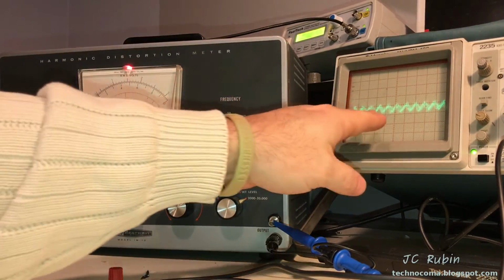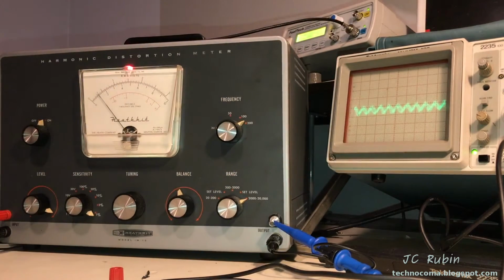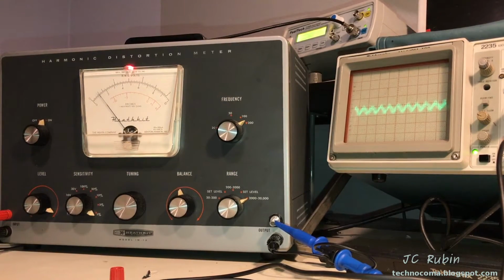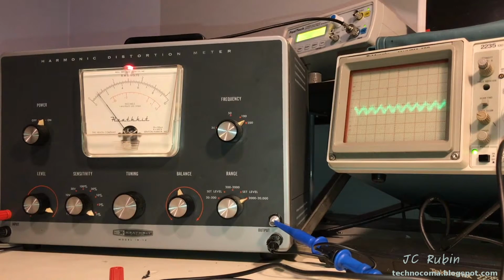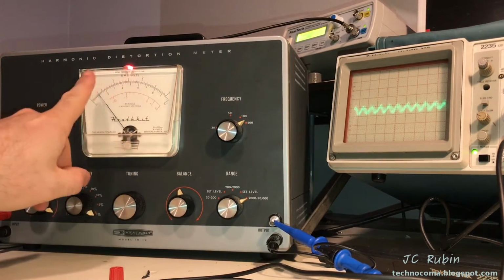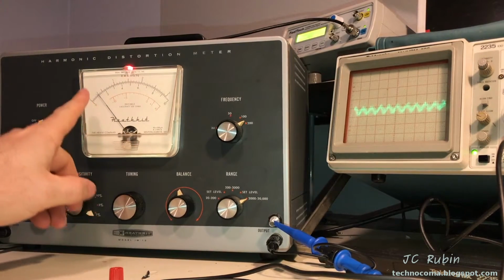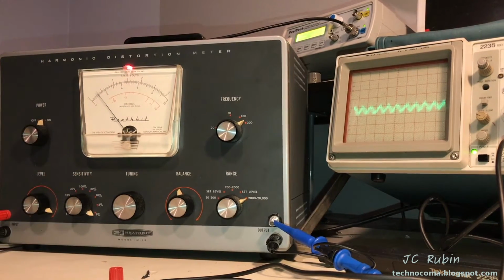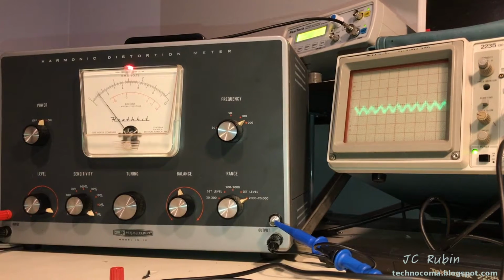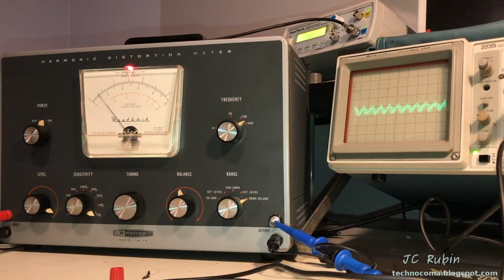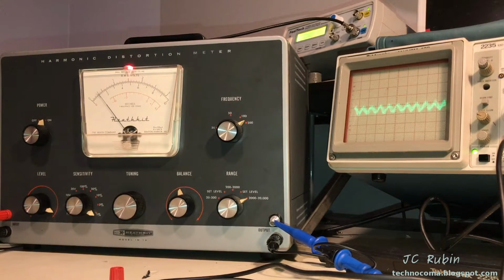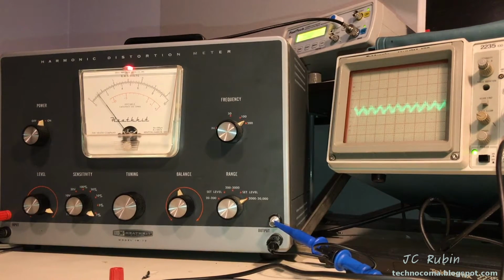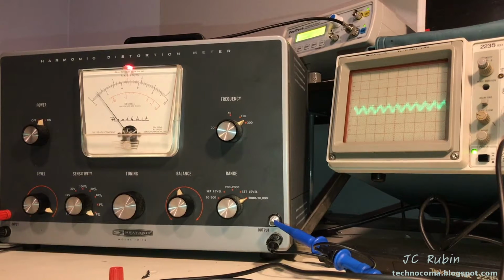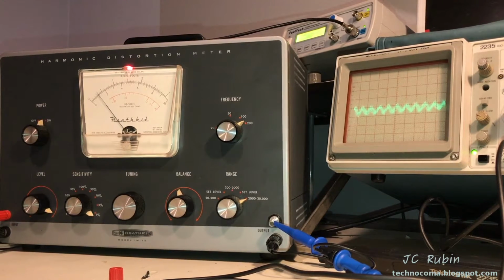So what we're left with is the distortion minus the sine wave, and with the 1% being the total deflection, we're seeing 0.11% total harmonic distortion for 15K. So that is how this unit works to measure the total harmonic distortion.